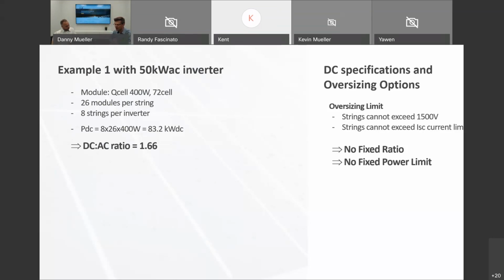Out of the box, the 50 kilowatt inverter has 4 MPP trackers, 2 strings each, which means we have 8 strings per inverter. And if we take the longest string design possible at 26 modules, we have the 8 times 26 times, let's say, a general 400 watt panel at 72 cell. We get already 83.2 kilowatts, which we can physically and electrically connect to that inverter, which leads us directly to a DC to AC ratio out of the box of 1.66.